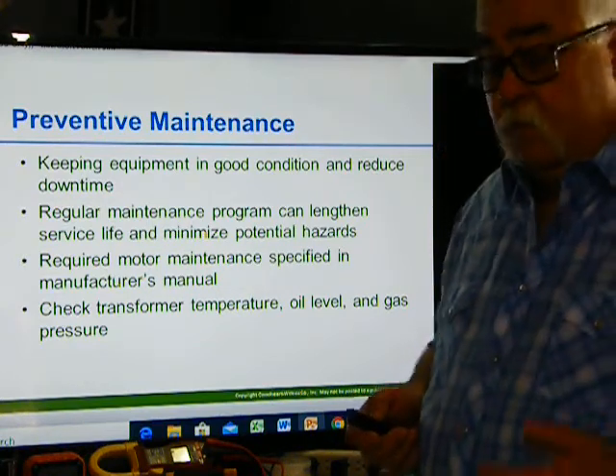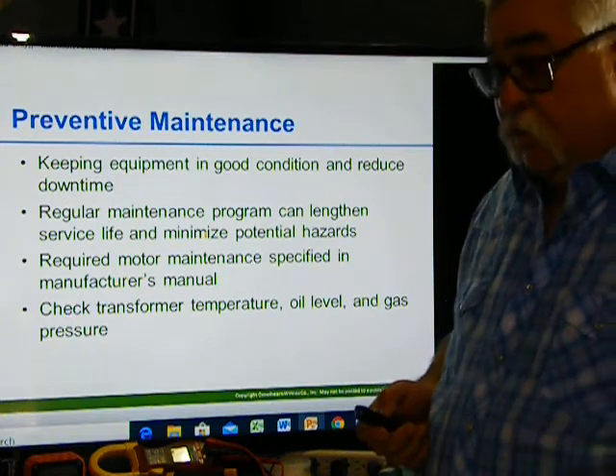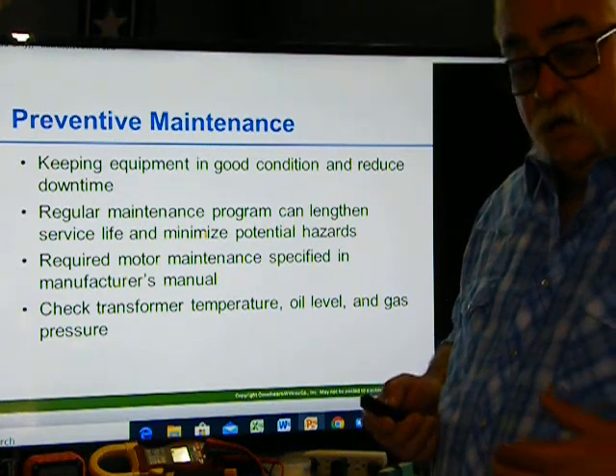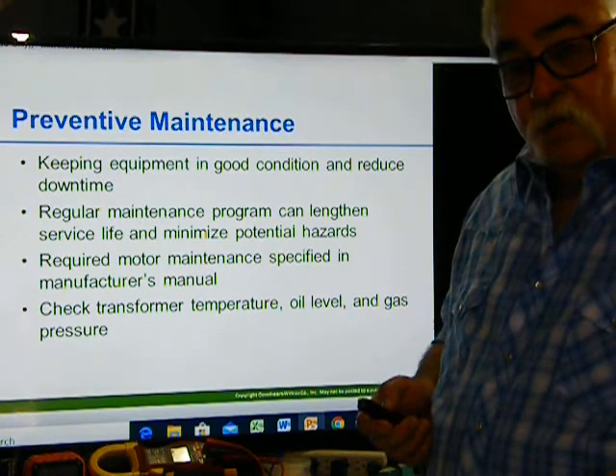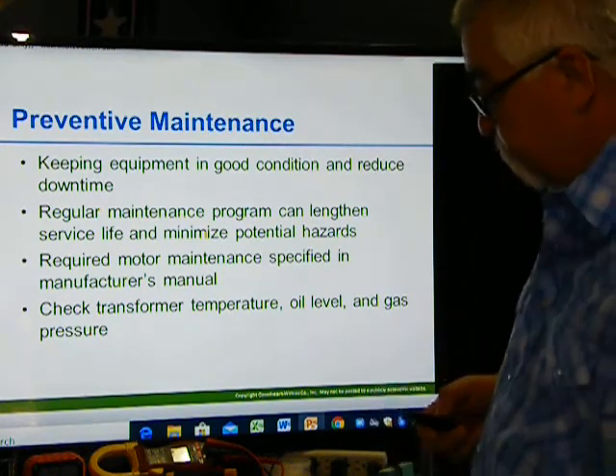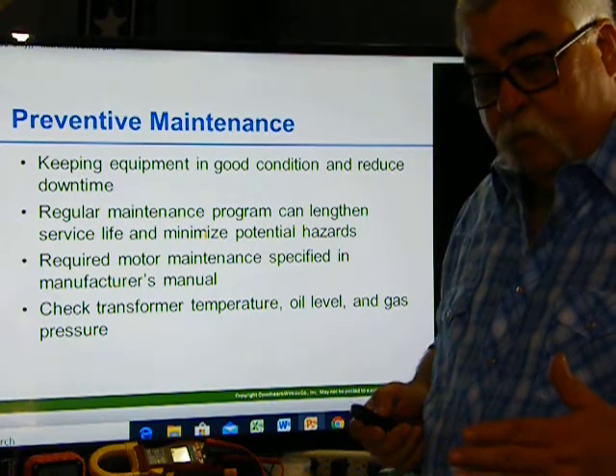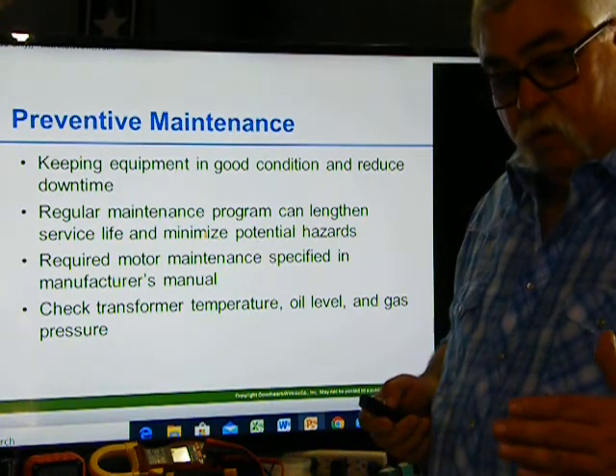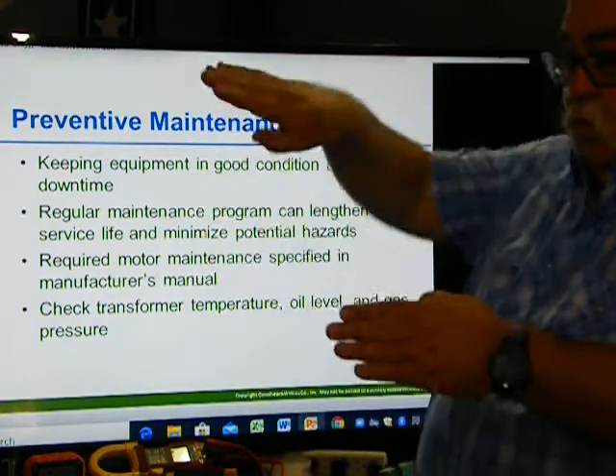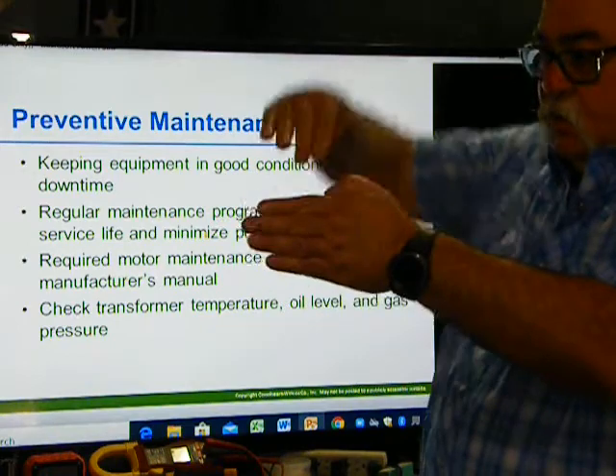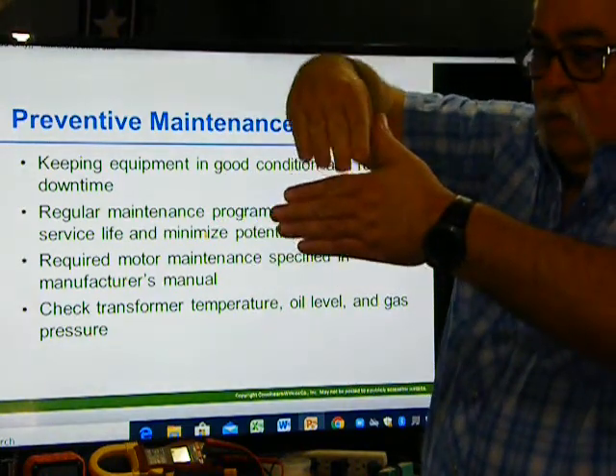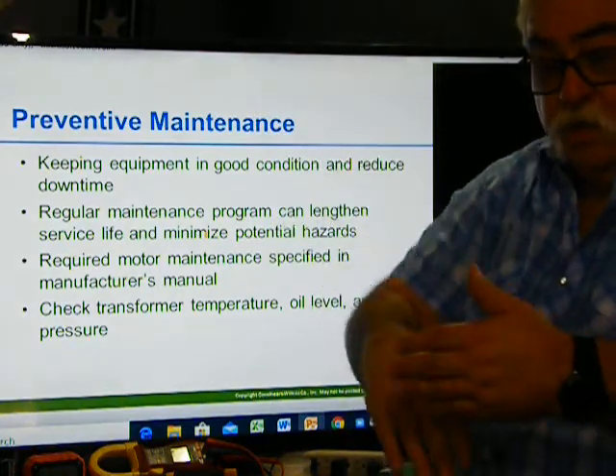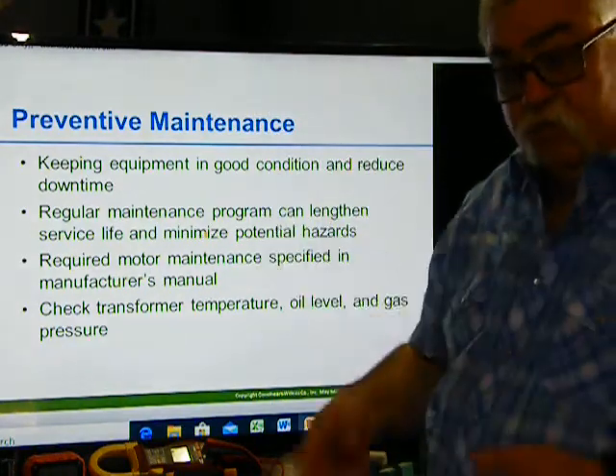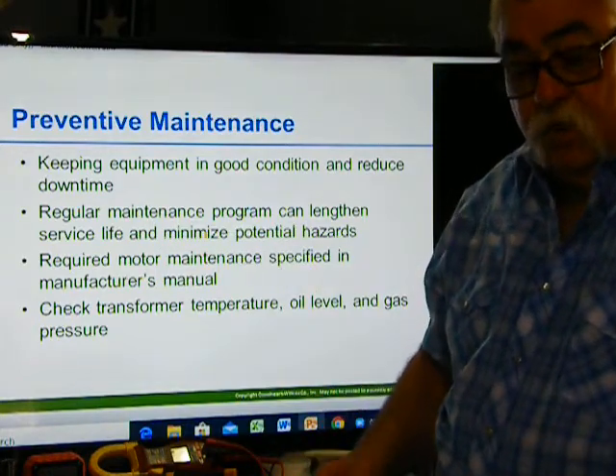If you have a dry type transformer, maybe clean it out every once in a while. Make sure there's enough air circulating so it's not too close to the wall, entrapping heat instead of releasing heat. We had one where somebody put the transformer all the way up against the wall. Where the fin came down, it hit the wall, and the heat was pushed down and then sucked right back up with a little bit of the air that it was circulating. Transformers start to get hot.